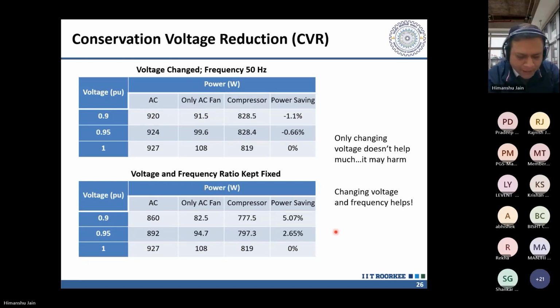Having done all these different analyses over the last 8-10 years, I haven't seen a case where harmonic distortion is a limiting factor for adding more inverter-based assets, whether on the load side or on the grid side. One can argue that we are still not at a very high penetration of these resources, so I would take it as a point that this is something we need to keep monitoring as we add more inverter-based assets. But I haven't come across any study where total harmonic distortion has become a limiting factor for adding more such resources.